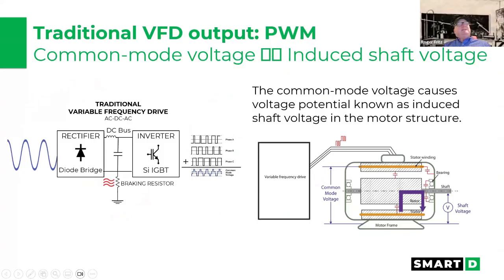So what they're talking about here is this common mode voltage, which is causing the bearing issues. That extra PWM and all this choppiness goes into the motor here, and it goes into the stator winding. But because the voltages are not common from one to the other, they don't cancel each other out, and you get a capacitance effect between it and the frame and it and the rotor. And so it creates what they call circulating currents that want to go through. And where they want to go through is the bearing, because that's the quickest path to get back.